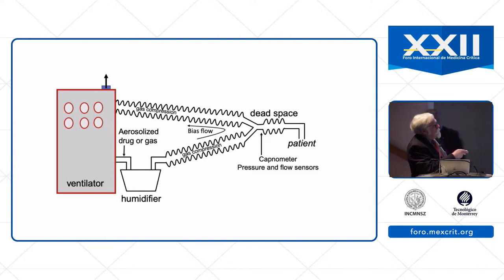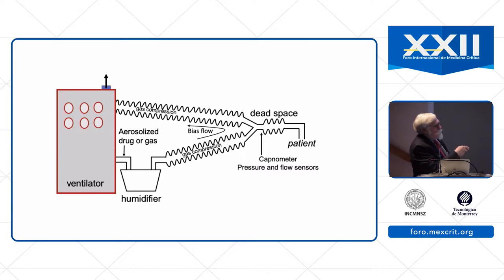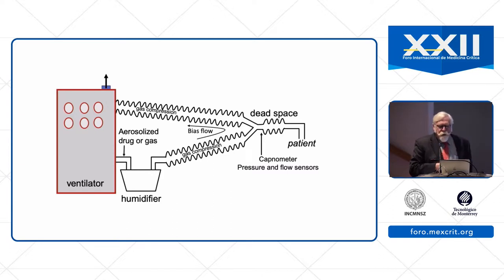We can insert monitoring devices like capnometers, pressure and flow sensors into the circuit. Most modern ventilators also place a bias flow through the circuit during exhalation, and that improves triggering.